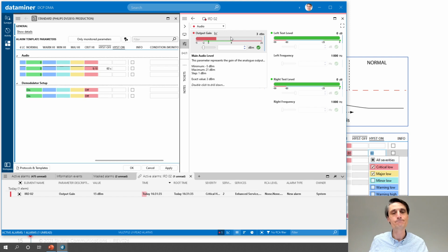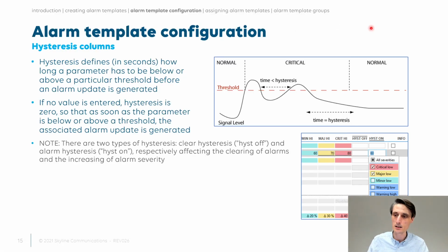It's a normal value. Well, maybe you have to wait a little bit until the hysteresis is over and the 60 seconds is gone before the alarm will effectively be taken away. So be aware of that confusing view you might see there. But as I said, the hysteresis is a very important feature to avoid alarm toggling, to avoid an excessive amount of alarms.